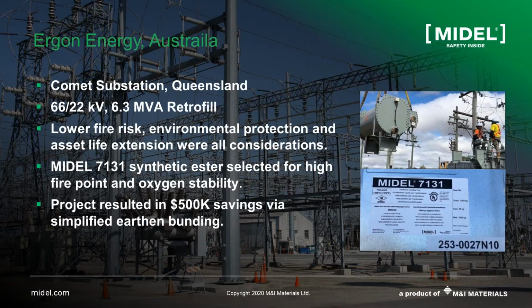To continue using mineral oil on this substation, they would have had to expand the site and install large oil containment. The introduction of MIDEL through retrofilling allowed for a simplified earthen bund arrangement that resulted in a saving of $500,000. This great example can also be found on YouTube, where all of the benefits realized are explained in detail by the utility. To do it full justice, I encourage you all to watch it.